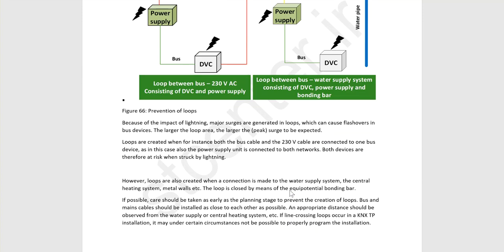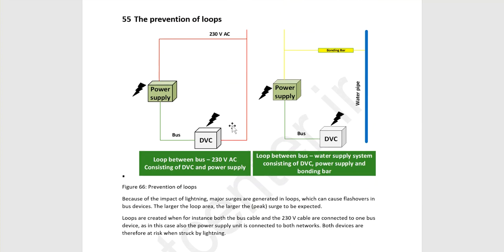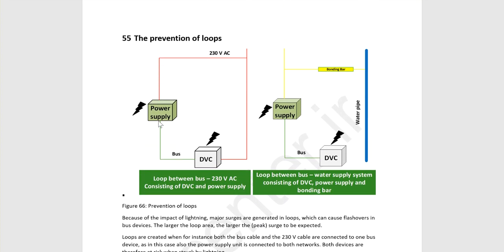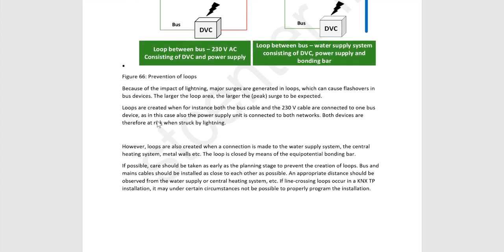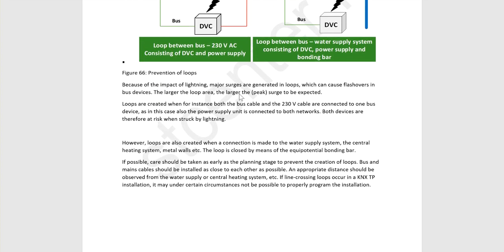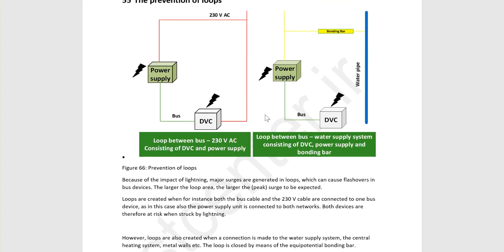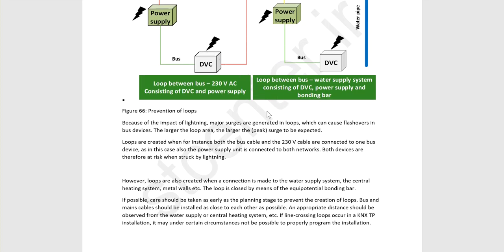Okay, so the next important thing is we should avoid loops, prevention of loops. Because of the impact of lightning, major surges are generated in loops. Okay, if this is too far from each other, which can cause flashovers in the bus device. The larger the loop area, the larger the peak surge to be expected. Loops are created when, for instance, both the bus cable and the 230 volt cable are connected to one bus device, like the power supply unit. You can see here.